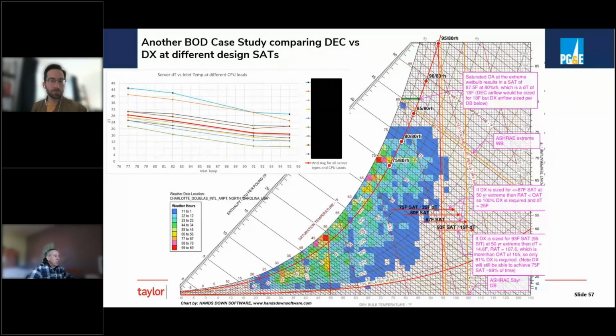And then we also looked at direct evaporative cooling, and we found that the worst case condition, which would be our extreme wet bulb temperature, which was, I guess, around 81 degrees, we would be supplying 87 degrees into the space, which would mean an 18 degree delta T that we would need to size our fans for. And so it just shows you the level of detail you can get to in terms of sizing the CFM of your air handling based on what supply temperature you're going to design for.